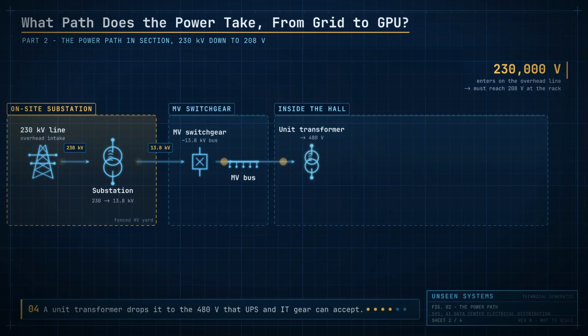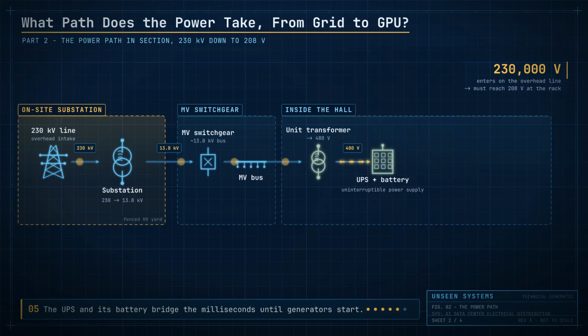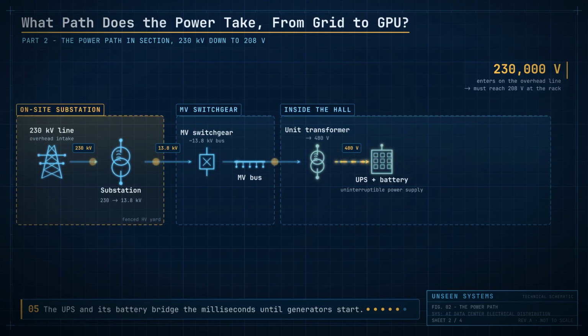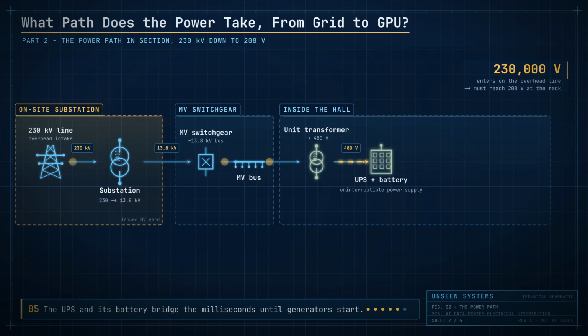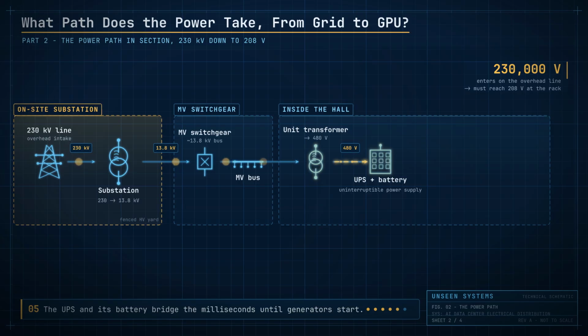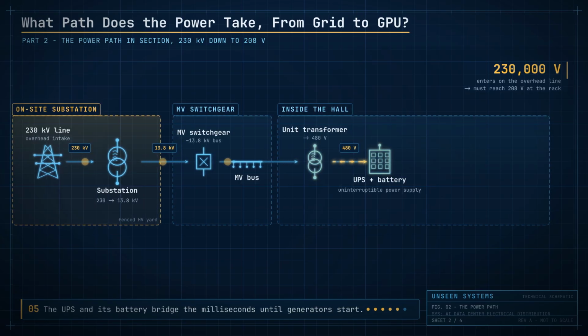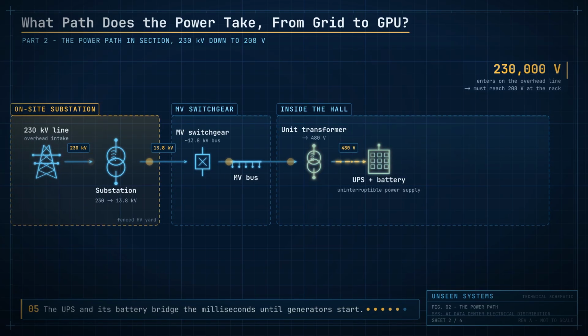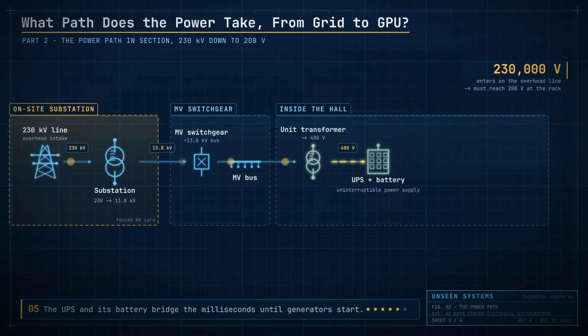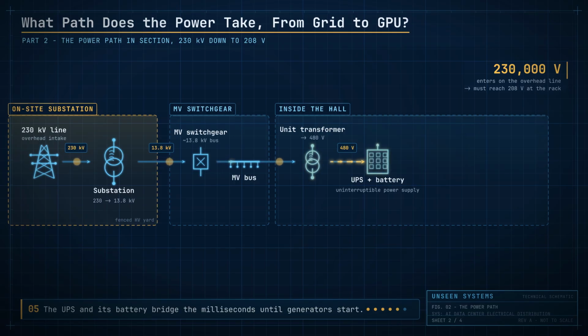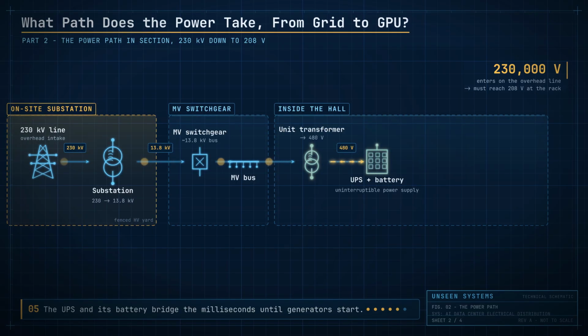Every transformer is a physical box, and each one gets smaller and more numerous as we close in on the chips. Next, the power passes through a wall of UPS units, uninterruptible power supplies, and their batteries. Their job is not to run the site for hours, it is to clean the power up and cover a blink. If the grid so much as flickers, the batteries carry the whole load from milliseconds to a few seconds until backup generators can start. Hold onto that row of generators. It comes back later, and it is the whole point.